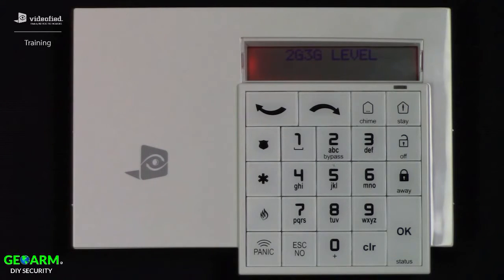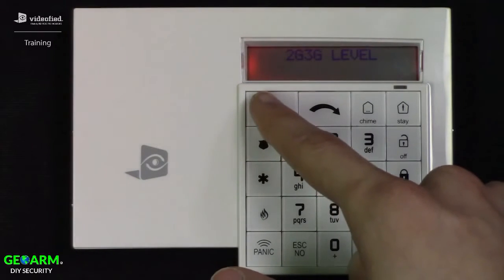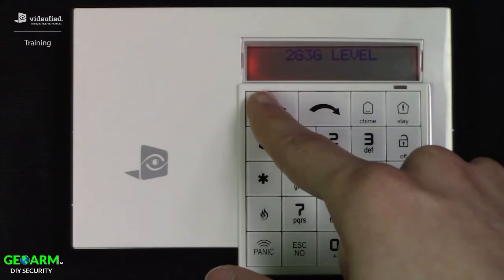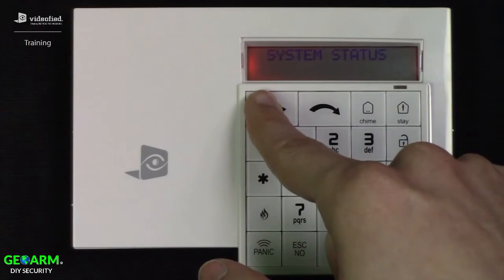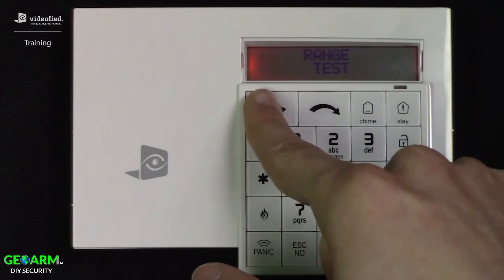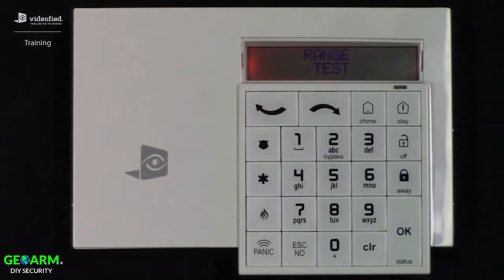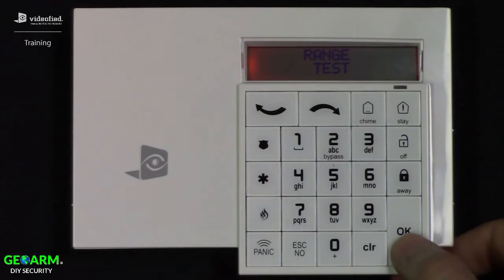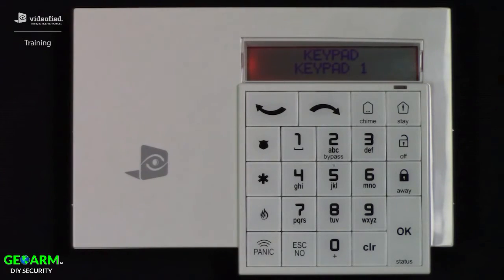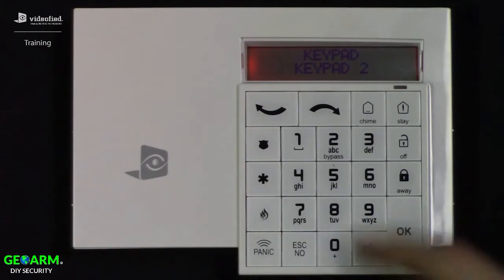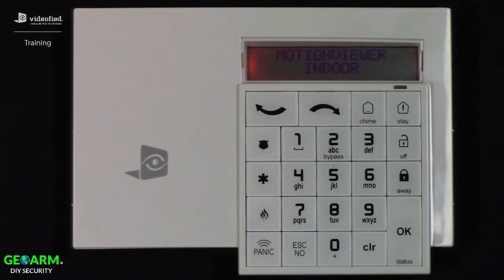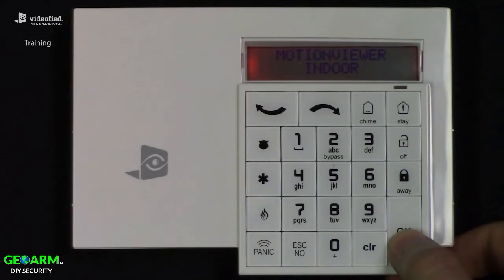Next, we can range test our devices. The range test will test RF performance bidirectionally between the control panel and the devices, and will display a result in real time as a number out of 9. Press OK to enter the range test menu, where it will provide a listing of devices currently enrolled in the system in the order in which they were enrolled. Scroll through the listing using the arrow keys, then press OK to initiate a test on a specific device.